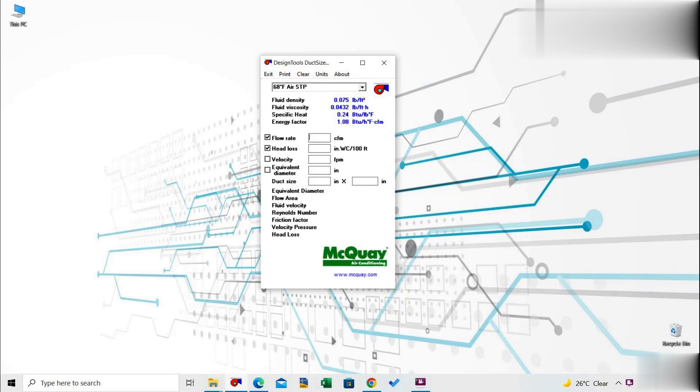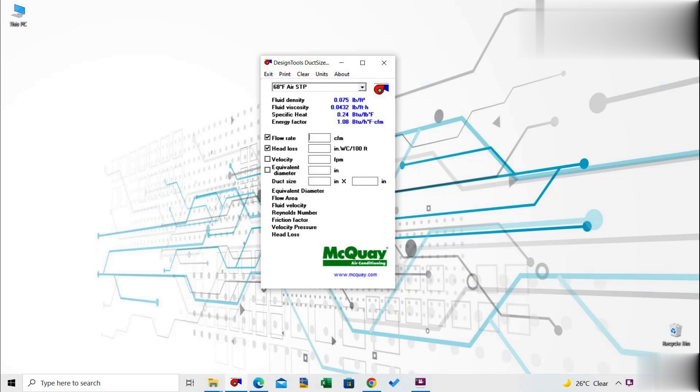It calculates the friction loss in a section of duct. The user can choose different types of duct construction in this program. The program allows the user to input multiple sections and view the overall results. In this video, I am demonstrating how to design a duct section using constant velocity method in McQuay Duct Sizer.